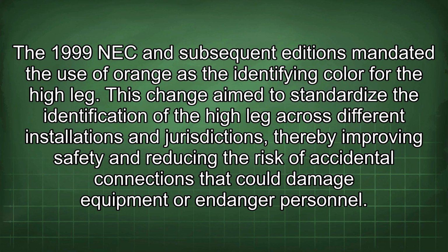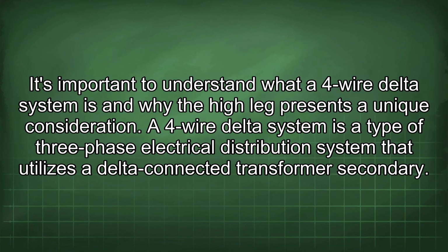This change aimed to standardize the identification of the high leg across different installations and jurisdictions, thereby improving safety and reducing the risk of accidental connections that could damage equipment or endanger personnel. It's important to understand what a 4-wire delta system is and why a high leg presents a unique consideration.